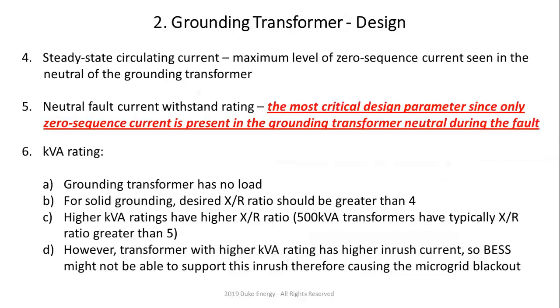When you have islanding, you're going to have some level of imbalance. So you have to design it with the steady-state circulating current maximum level, which is a function of the typical imbalance. Now, when you have motors inside your microgrid, you have to make sure that your imbalance is no more than 15%, because some of those relays are probably set at 15% imbalance. Also, for the battery energy storage system on its own, if they're set on imbalance, which is a 46 setting, you're going to see that it's set at 0.8.